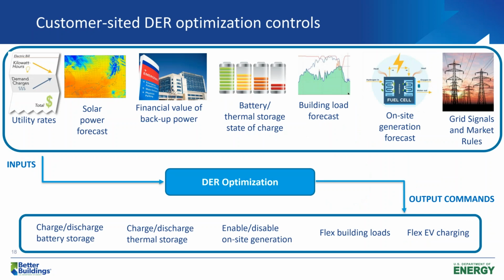The other piece to this puzzle: you have DERs, either microgrid or grid tied, and you have optimization controls. Think about everything that needs to be considered when deciding whether to charge or discharge your battery storage or thermal storage, enable on-site generation like CHP (although that may be baseload in any case), flex your building loads, or flex your EV charging. These are the levers we have to change in order to minimize costs.